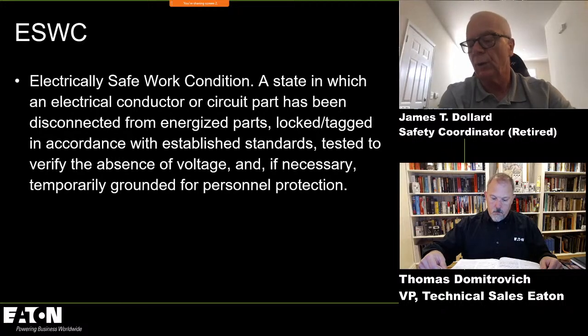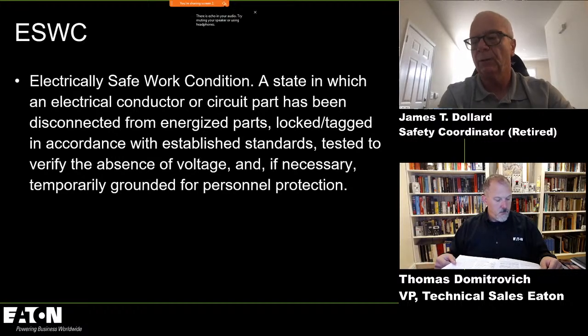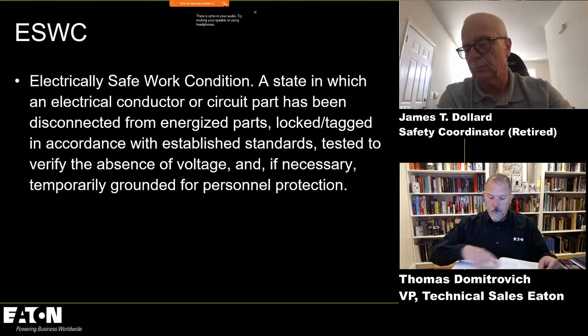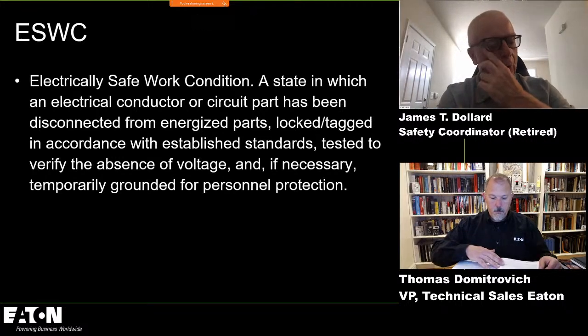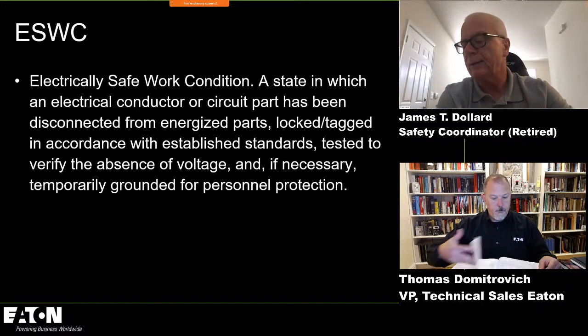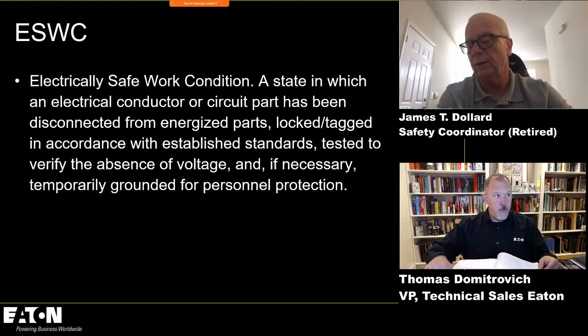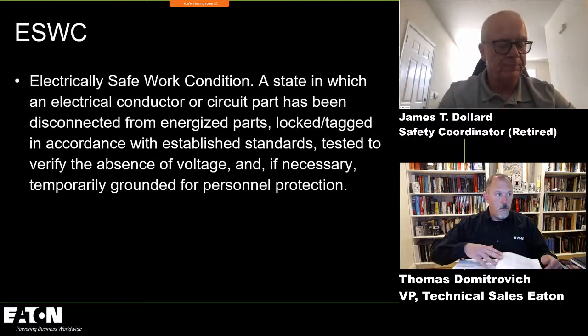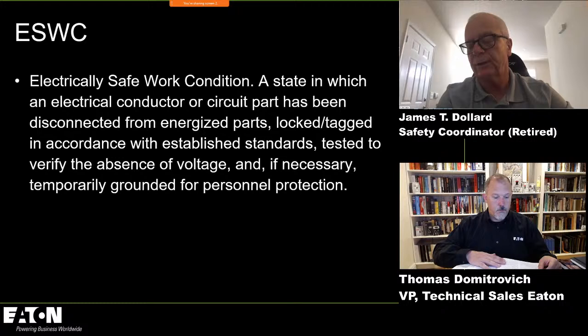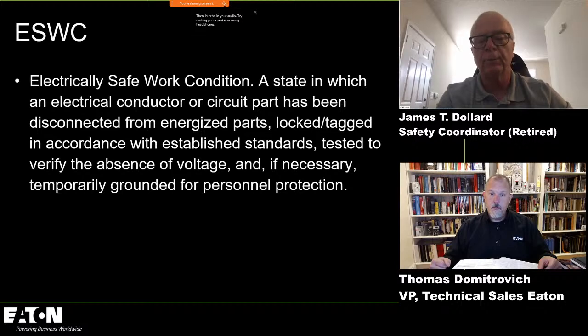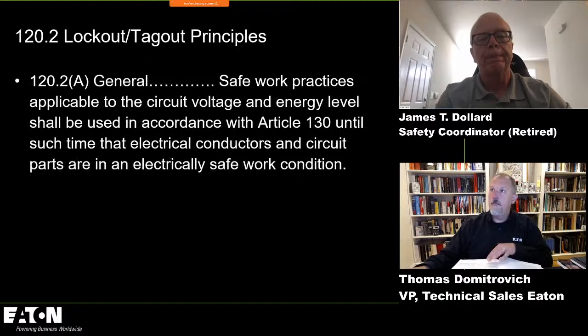And it's very interesting when you go into your likelihood table, you'll see that the application of temporary protective grounding after verification of absence of voltage is considered to be interacting with the equipment in a manner that increases the likelihood of an arc flash. So you have to have all your PPE on to perform that task. And the reason is that the committee looks at it and says, if you made a determination that you need temporary protective grounding, then we need that individual wearing all their PPE until it's applied. Yeah. Yep.